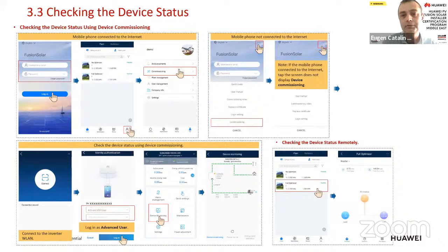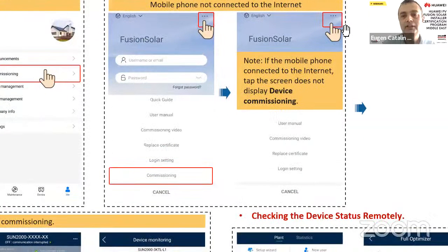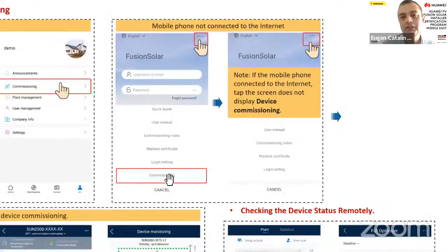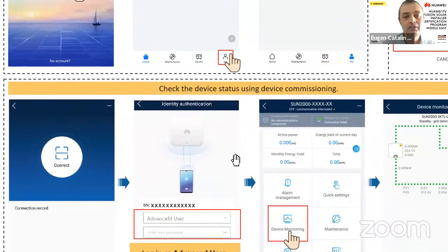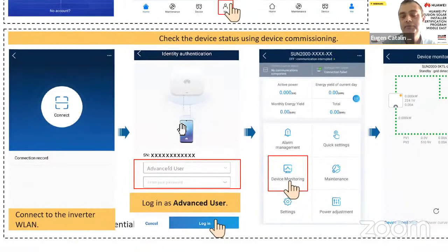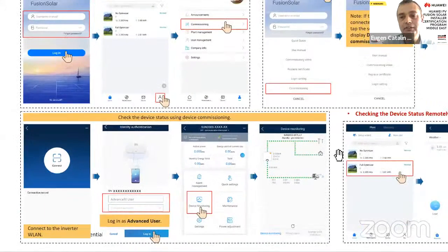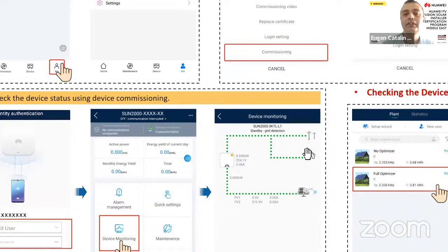I have another option. I disconnect my phone from the internet and connect the phone directly to the inverter Wi-Fi, open FusionSolar, and log out if I am logged in. On the main page there are three dots. If the phone is not connected to the internet, the commissioning device option will be available to open the local SUN 2000 application. Connect to the inverter. You can scan the QR code with the serial number of the inverter, and enter the password. If you know the password, go to device monitoring and we can check, for example, the status of the inverter.